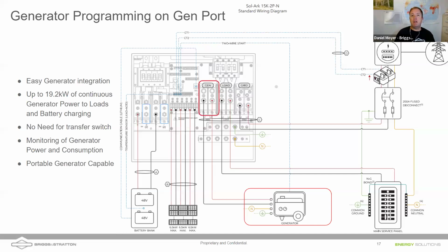So the first way we're going to talk about it, and I think this is probably going to be one of the most common ways we're going to pull a generator into a Sol-Ark or a lot of the other hybrid inverters, is on the gen port. So at the top right, we have our grid, our meter can. We're going to have our disconnect feeding into the grid. We can bring all 200 amps in, 200 amps right back out on that load port into our load distribution panel. We're going to land.